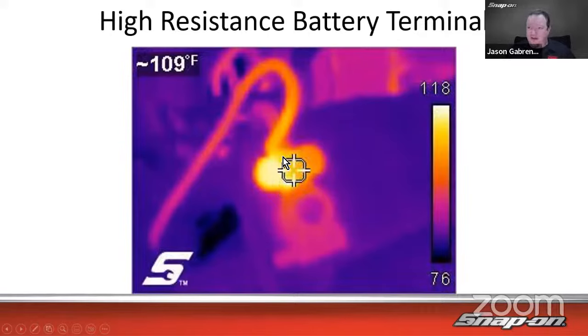So we can see how the wire there is rather warm, very, very warm. 118 degrees, 109 in the middle. So 118 degrees Fahrenheit there. That's pretty darn hot. And when we have high resistance, such as in this case, it will generate heat. So that's how we can see that. We see the heat.